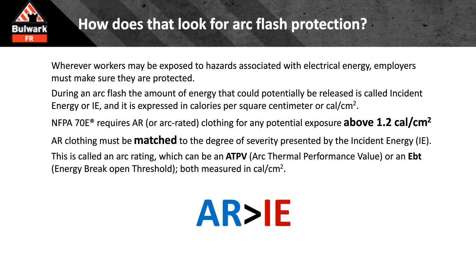So how do we simplify it? Everything you read on arc flash protection, just understand you want to have more arc rating than incident energy. Incident energy is measured in calories per centimeter squared, and your arc rating is measured in calories per centimeter squared. What it tells you it will blow up at, you want to have more to insulate and protect you, i.e., more than the incident energy. If that gray box, or that overhead line, or that pad mount transformer, when the engineers do their work, tells you that's 5, 6, 7 calories, have more on your outermost layer. That's all you have to do from a simplification standpoint.